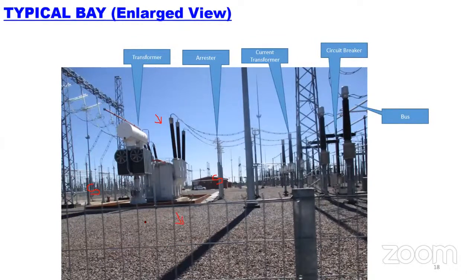If you look at the ground, there are stones placed on it. Below ground there is an earth mat, called the conductor, placed about 1 to 1.5 feet below ground. Above ground they put a 150 mm layer of gravel, like a bed, to distribute the fault current when there is a fault within the station. So the person standing on the field is protected, since the current is distributed and they are not electrified.